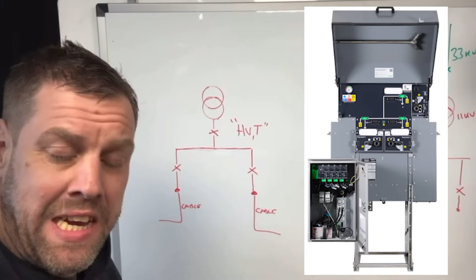Right, here's a drawing of an HVT. It's a unique piece of switchgear manufactured for the very reason to be a T. What happens is, those cables there - I'll remove those - that's what you get. So you've got a leg here that's in or out, doesn't really matter if people call them in and out. A leg here that's in and out. Then off that you've got a piece that comes off, and the T - there's the T - that goes to the transformer.